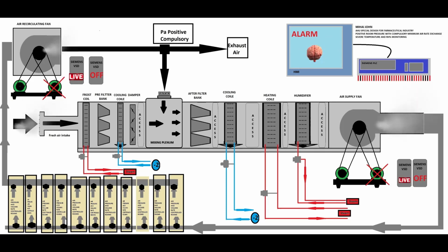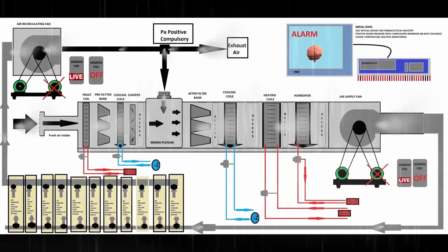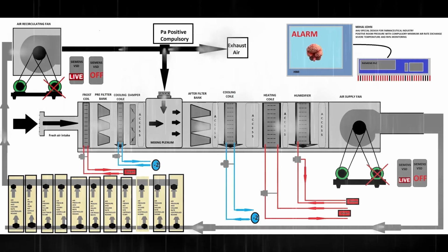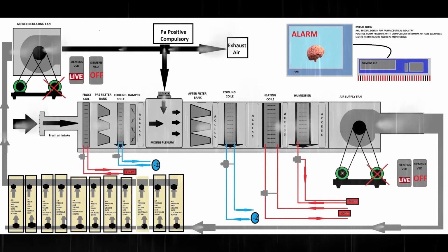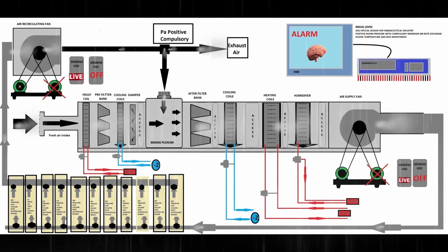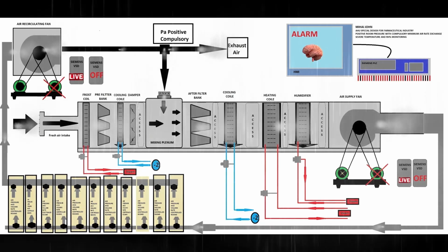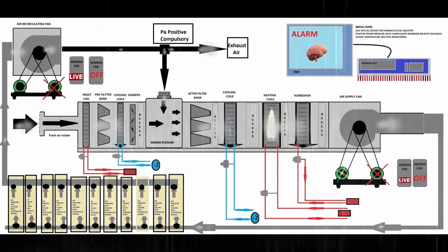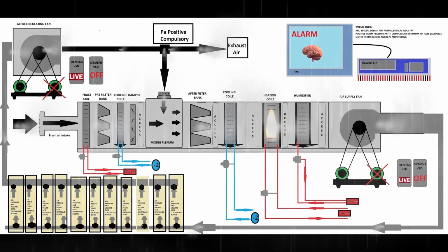Now we have to find a solution to overcome potential problems like humidity, high temperature, low temperature, and so on. So just imagine you have a rainy day, the humidity is very high outside. In that case, how can you remove the absolute humidity? You will obviously start the primary cooling coil, because a lot of condensation will happen there and the air will lose a lot of moisture.